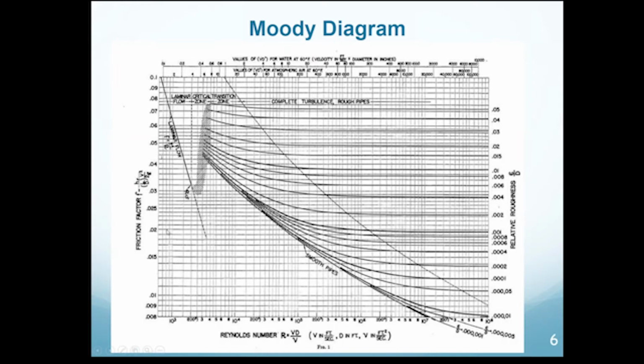That diagram is used to find F, the friction factor for the head loss equation. If you have the velocity and diameter of the pipe, you find Reynolds number. If you know the roughness of the pipe, epsilon, based on the material, there are tables in books or online to help you find it. You divide it by the diameter to get a dimensionless number called relative roughness. So if Reynolds number is 10,000 and relative roughness is 0.002, you follow the curve up, meet the value 10,000, then go across and read the F value, which is 0.034. Remember, this is a logarithmic scale. So F equals 0.034, and F could range from around 0.01 to around 0.08 or so.